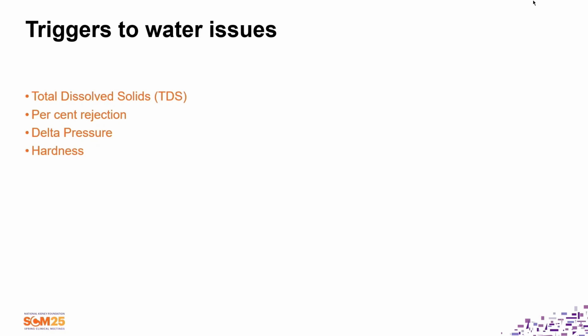And the reason why you do have to take action on these trends is why? You don't want to get to the point where the facility's machines say, no water, alarm. Yeah. So those, and then hardness. Hardness is to protect the RO membrane rather than the patient. So this actually allows us some liberty in taking action. You can actually run hard water through your RO membrane effectively without harming patients. Okay.